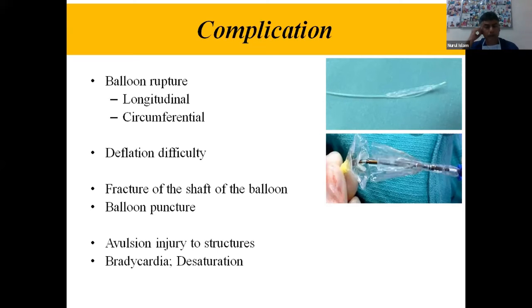And if the balloon is kept for a long time inside the packet, it can cause fracture of the shaft. It happens very rarely, but you have to be very careful. And balloon puncture: if you are taking a smaller balloon and you put the hard, stiff end of the guide wire, by mistake the balloon over the shaft catheter can get punctured.